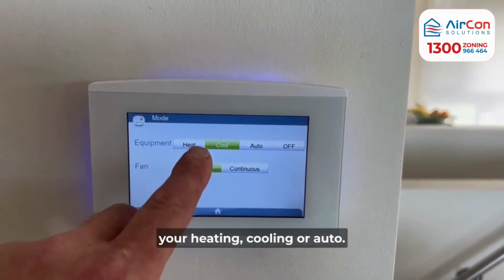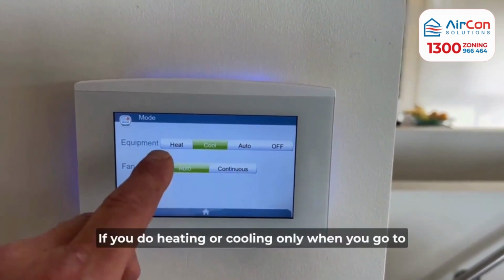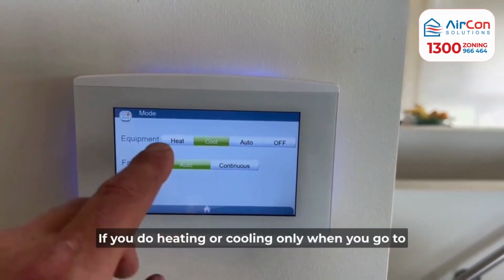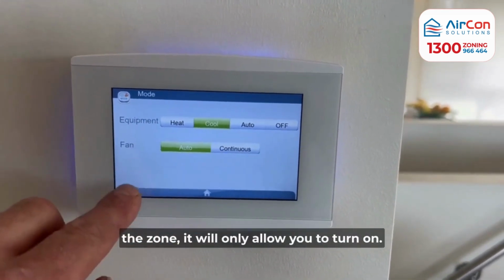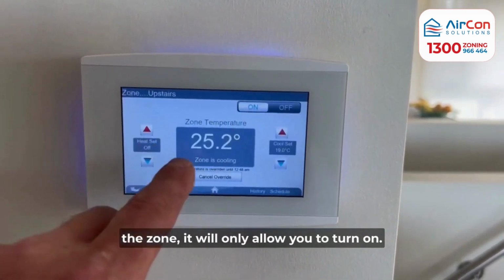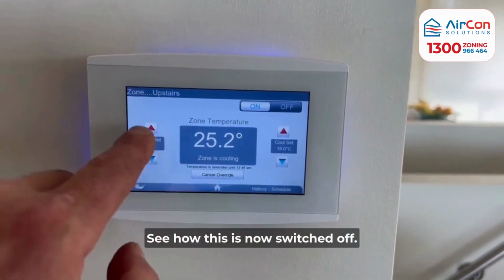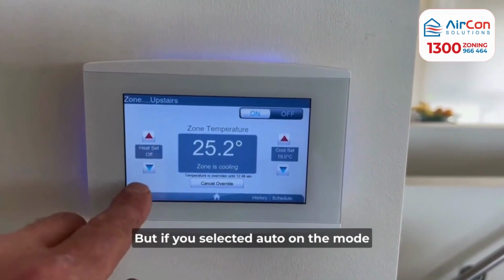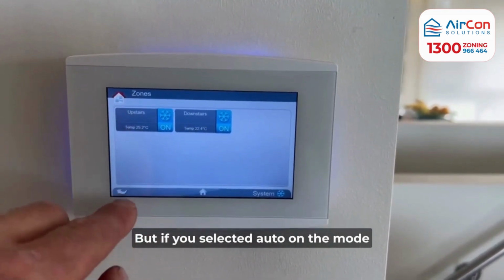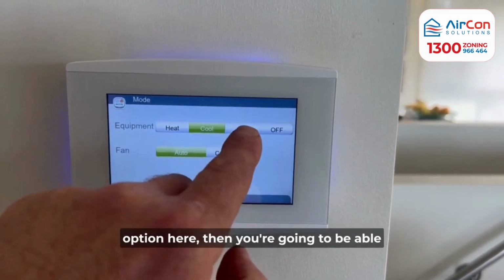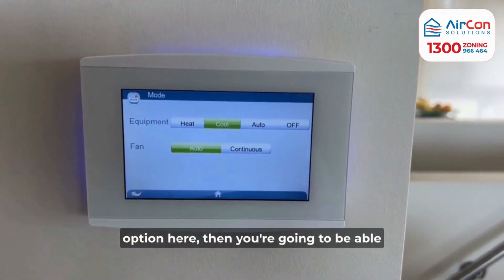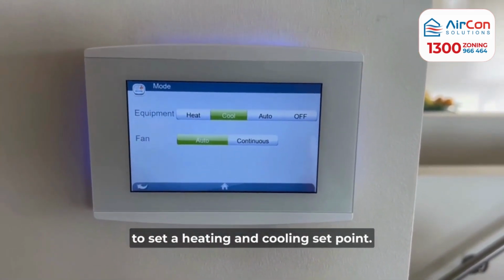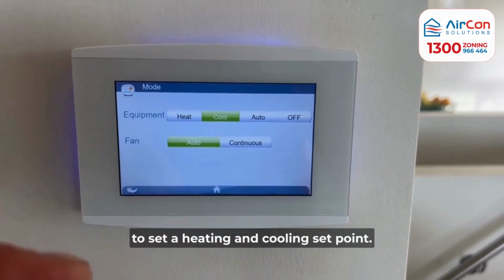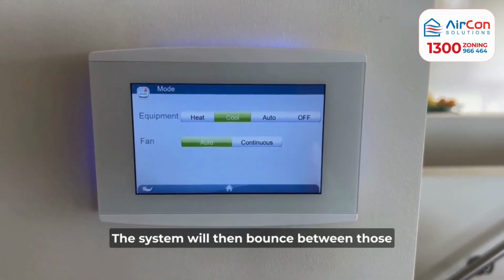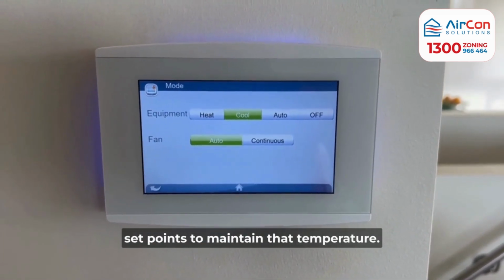This is where you can select your heating, cooling or auto. If you do heating or cooling only, when you go to the zone, it will only allow you to turn on, adjust that one. See how this is now switched off. But if you selected auto on the mode option here, then you're going to be able to set a heating and cooling set point. The system will then bounce between those set points to maintain that temperature.